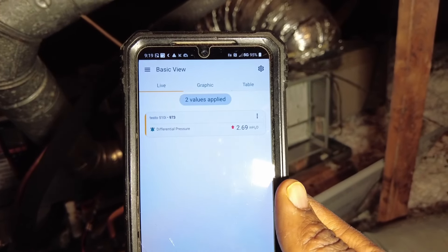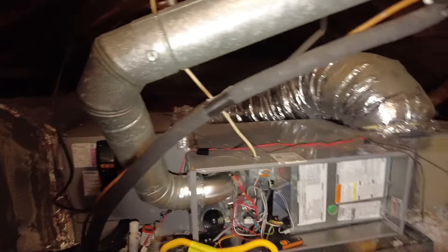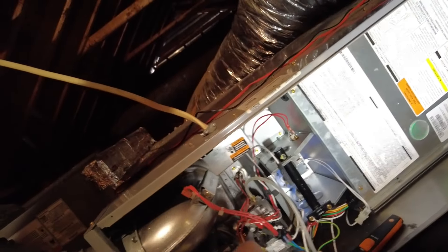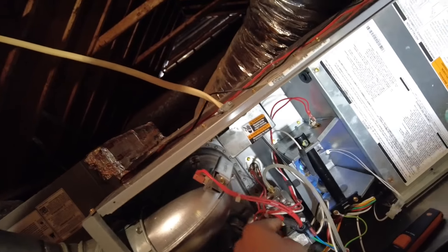Now we're checking the inlet gas pressure. Got my manometer set up there. That's low — 2.69 inches WC. Let's start combustion analysis again. I want to get it to about 3.0 to 3.6 or so. Hopefully it doesn't bring the CO reading back up.